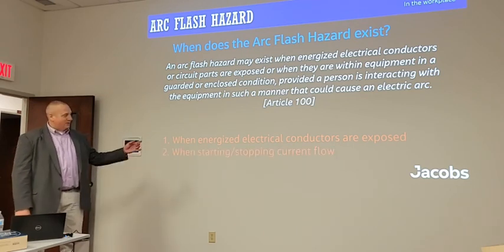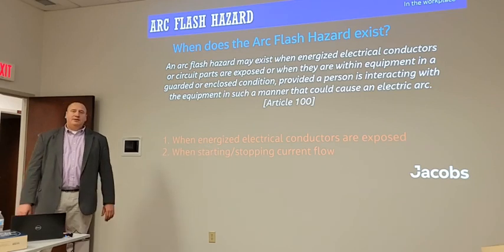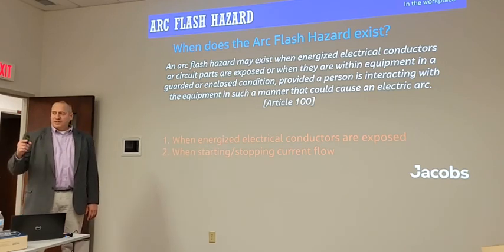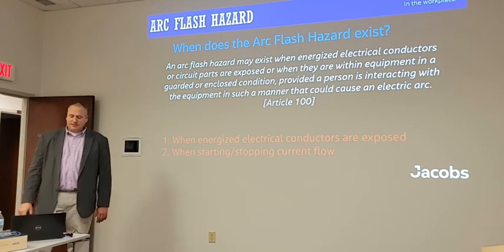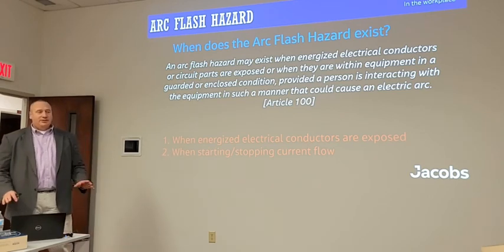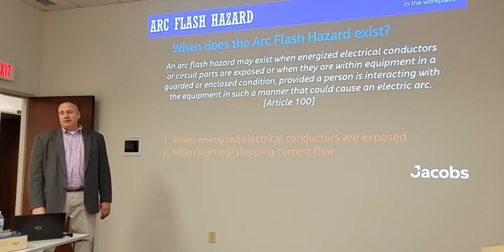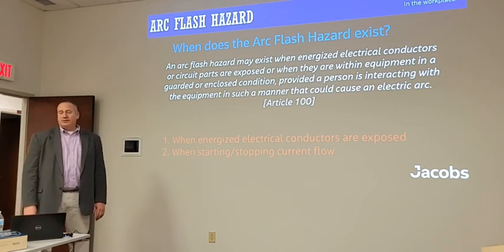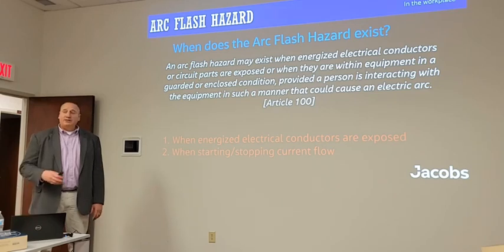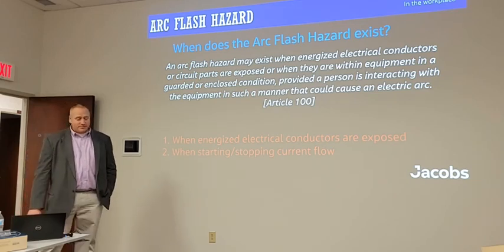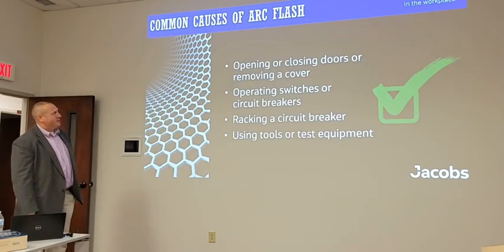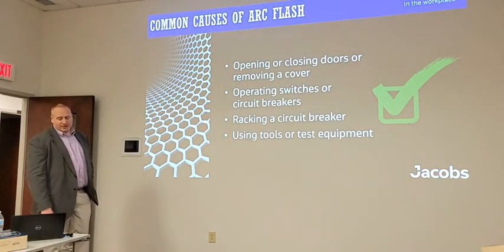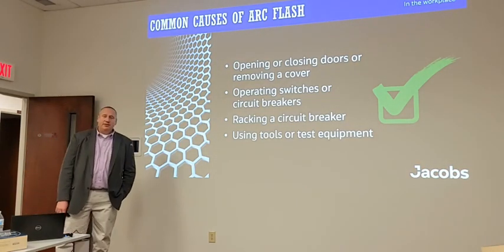The other is when you're starting or stopping current flow. If you're operating a breaker, pushing an open or close button, operating a disconnect switch, anything that starts or stops current flow, then on a three-phase system there is a potential for an arc flash hazard. You need to do an evaluation to assess that risk. Some of the common causes that we see with arc flash is opening or closing doors or removing a cover.